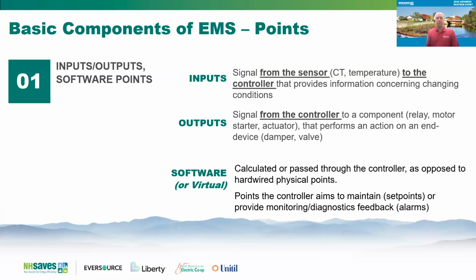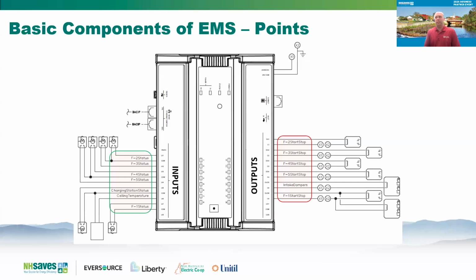And then you have software points. Those are just calculated points, such as a set point or an alarm or other non-physical calculation points. So here's an example I like to highlight of an actual controller graphic where you've got all the inputs on the left-hand side and all the outputs on the right-hand side. And you can see that there's fan status points on the left on the inputs, and on the output side there's damper actuators and fan start stops or command points. So I just really want to highlight the physical nature of a control system. So next time you're opening up a panel in a controller, take a look at what the inputs and output points are.